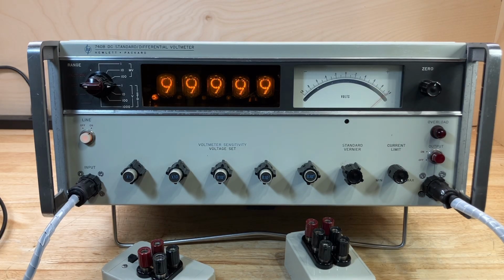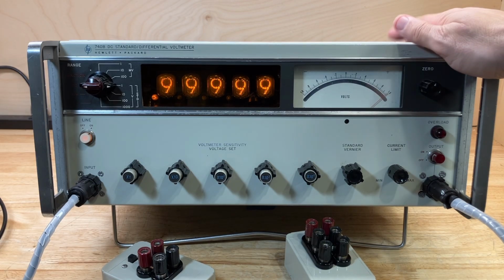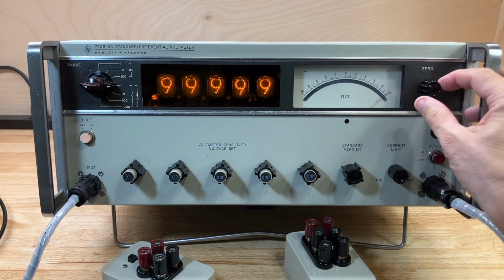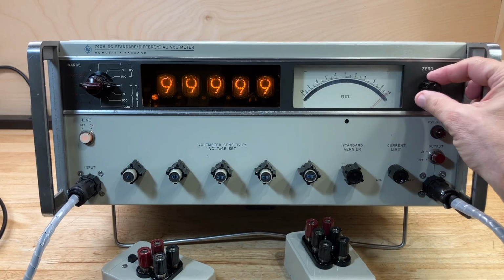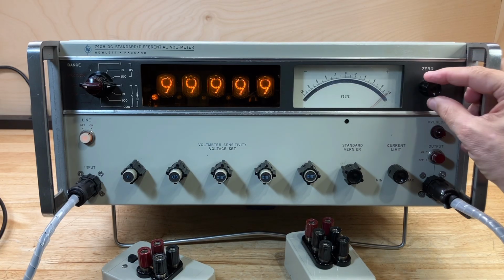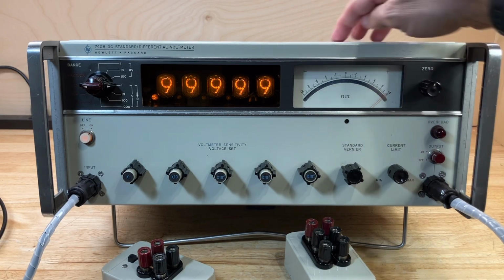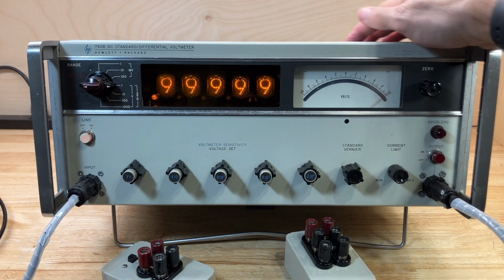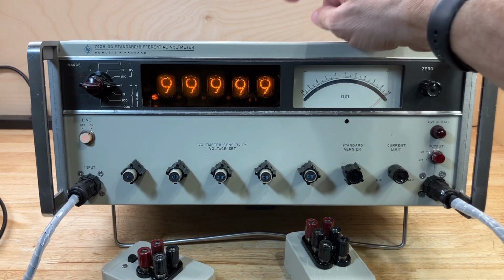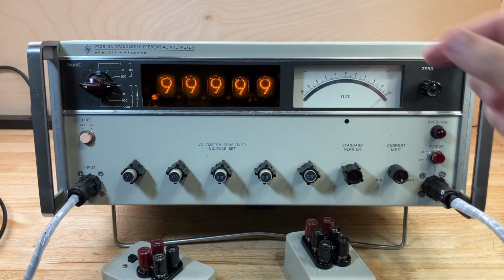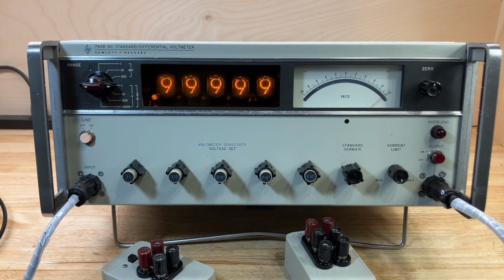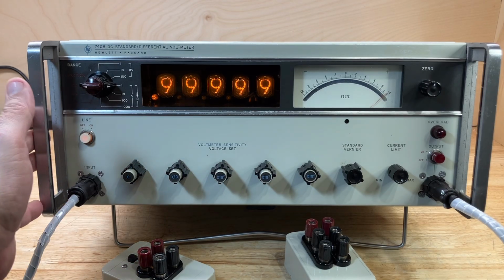Now I've done some other things internally to the instrument. Inside the instrument, there are actually two mercury cell batteries. One is to add a tiny DC offset for the zero adjustment, and that one is located up in this part of the instrument internally. And there's another one that's internal to the instrument towards the rear on the underside, and that one is used for part of the calibration and testing procedures internally to the instrument.